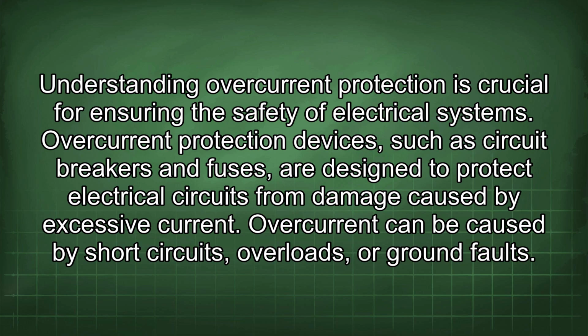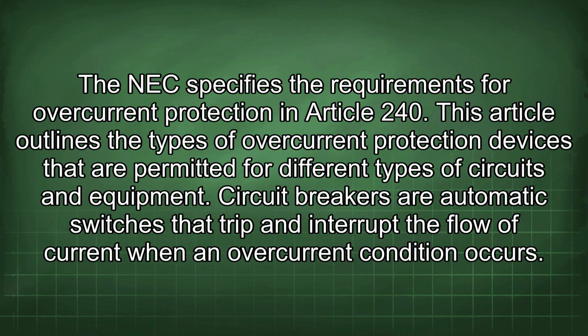Overcurrent protection devices, such as circuit breakers and fuses, are designed to protect electrical circuits from damage caused by excessive current. Overcurrent can be caused by short circuits, overloads, or ground faults. The NEC specifies the requirements for overcurrent protection in Article 240. This article outlines the types of overcurrent protection devices that are permitted for different types of circuits and equipment.